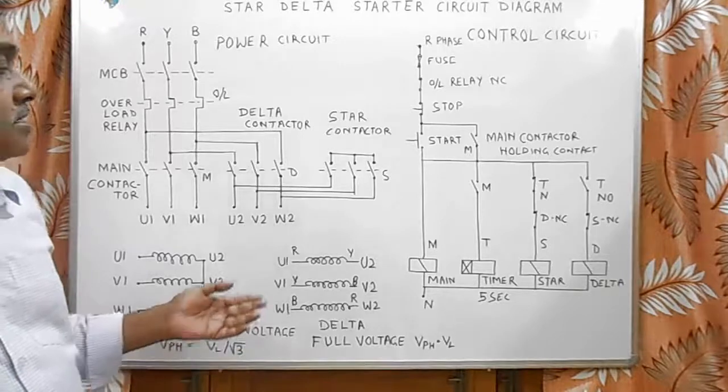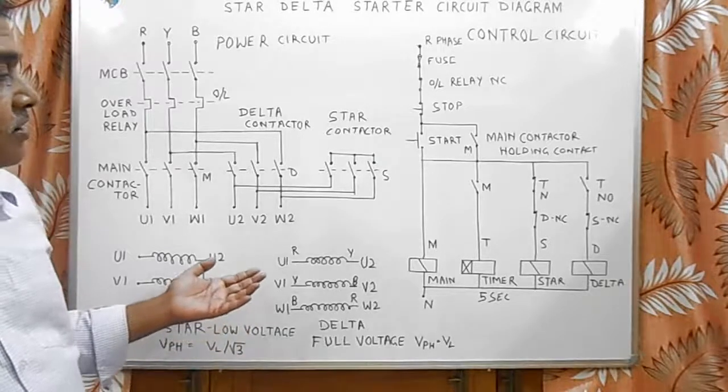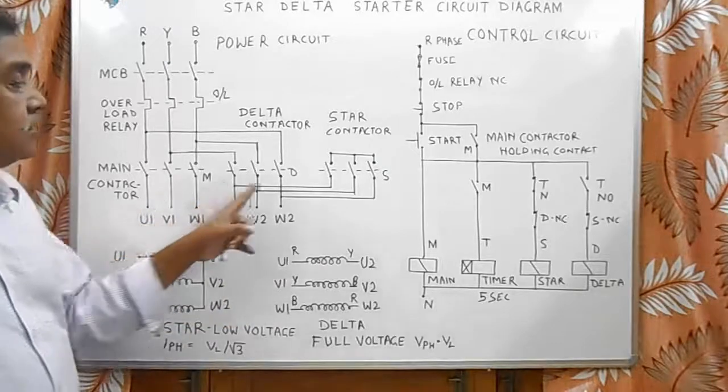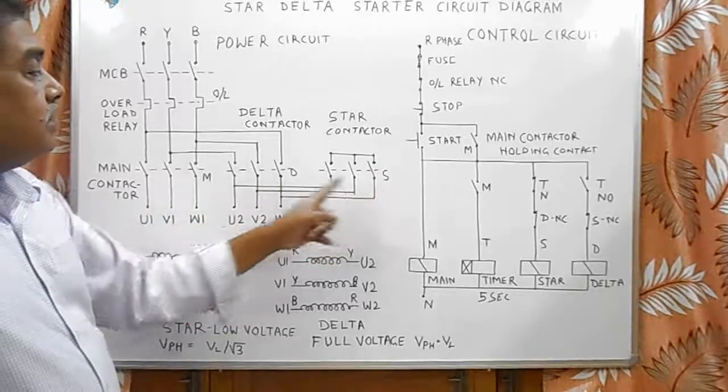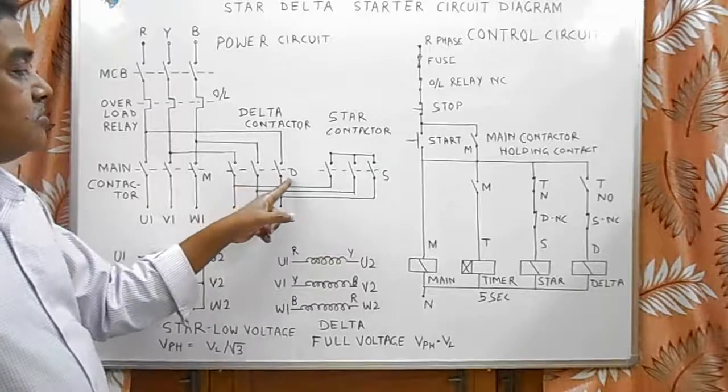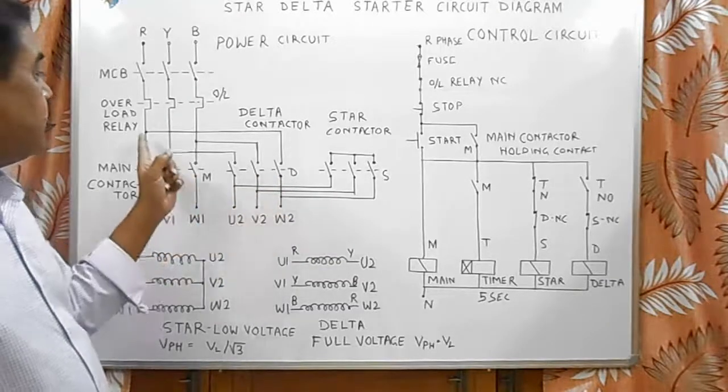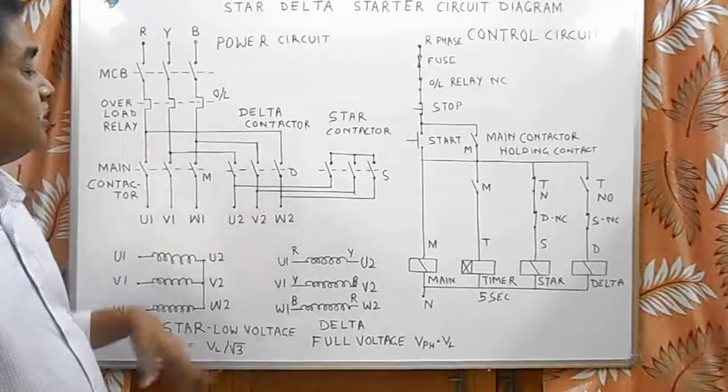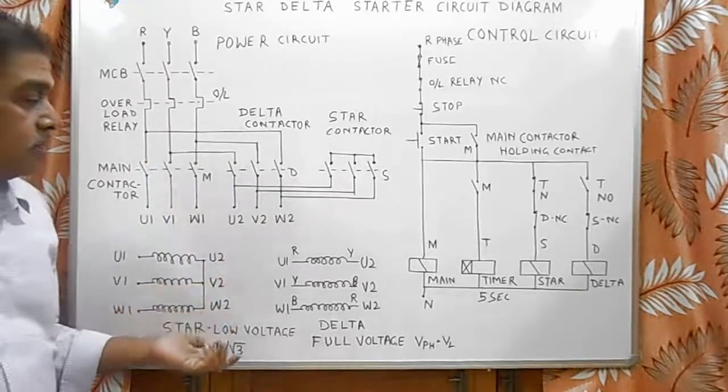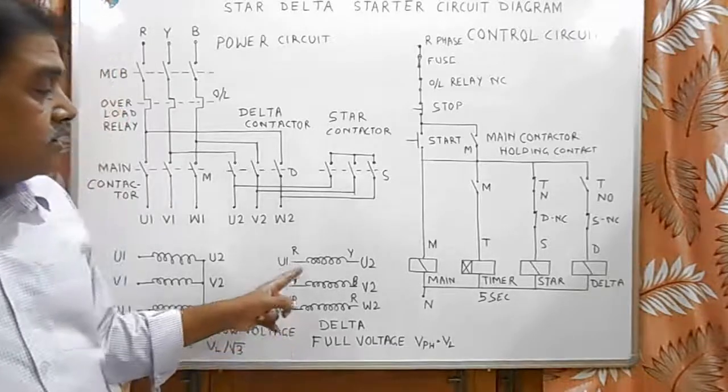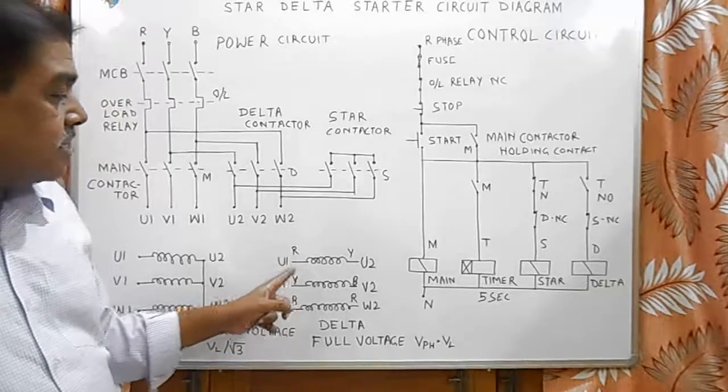After starting the motor at low voltage, when we want to run in delta, the star contactor is dropped and delta contactor is switched on so that U2, V2, and W2 receive supply. In that case, motor receives full voltage, meaning phase voltage equals line voltage.